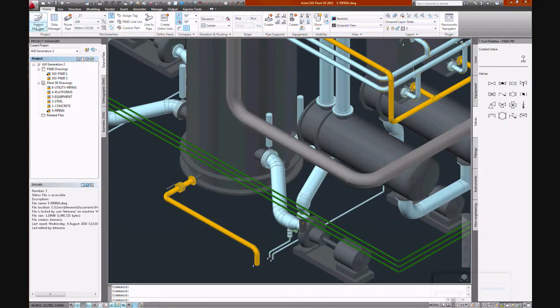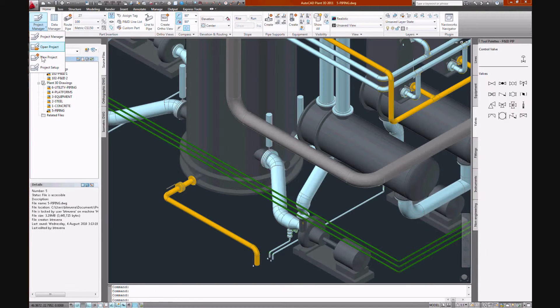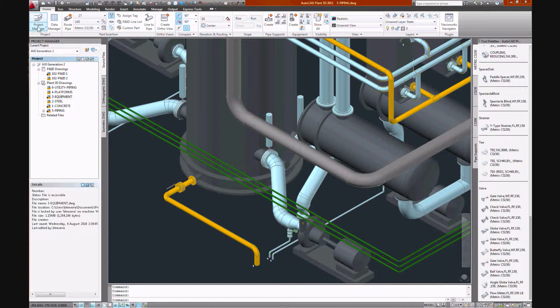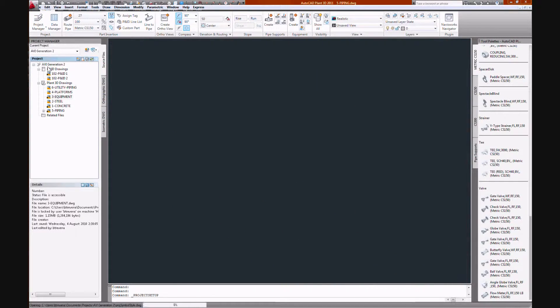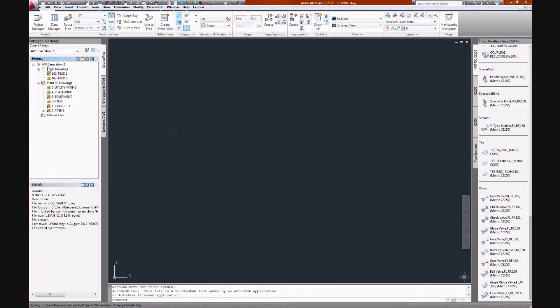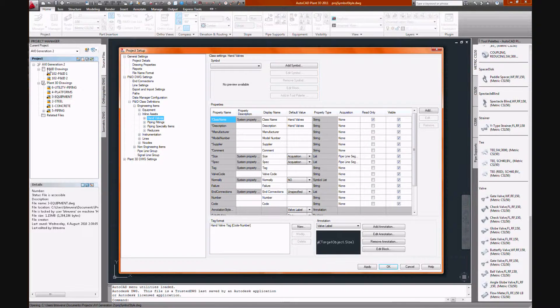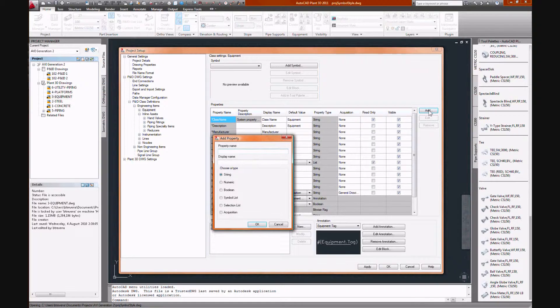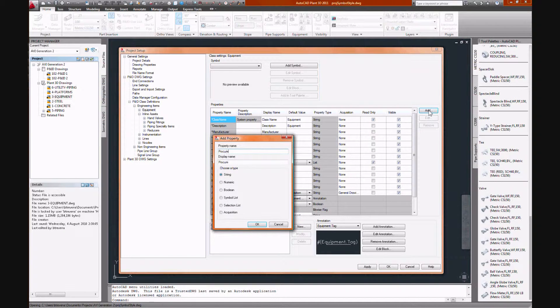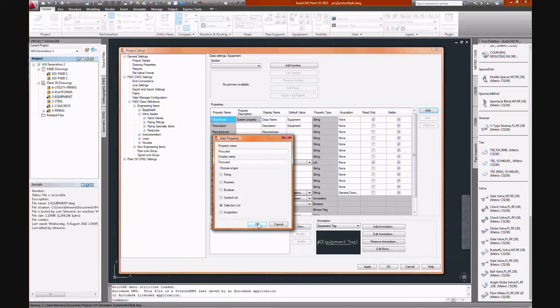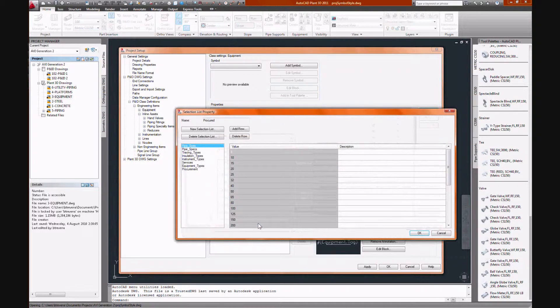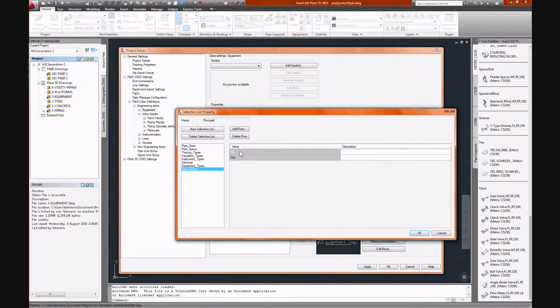It may be that you'd like to add procurement information to your report so we'll add a field to collect this data. So let's add procurement to our hand valves so open up project setup. Navigate to hand inline items hand valve class, click the add field button, name the field and we'll make it a list field and the two values in the list will be yes and no. Preset default will be no.